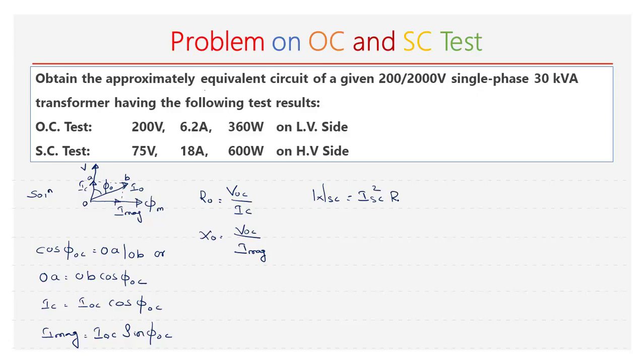From the SC test, WSC is equal to ISC squared into RE on the HV side, because the SC test is conducted on the HV side. It can also be written as ISC squared into RE2. The equivalent resistance referred to the secondary, RE2, is given by WSC divided by ISC squared.